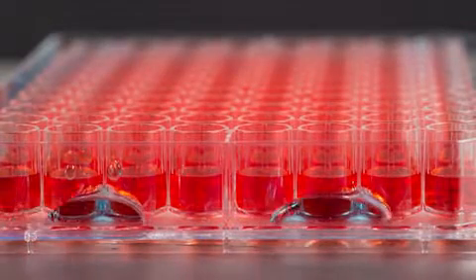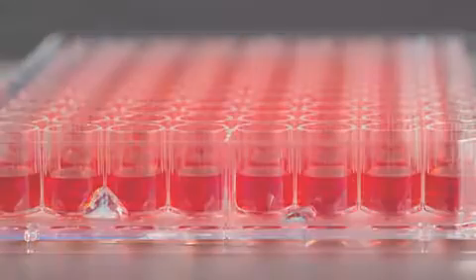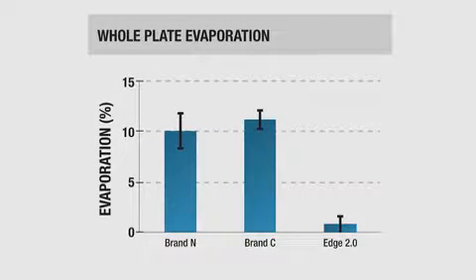Especially from the wells along the edge that are more susceptible to humidity change. The data shows that the Edge Plate significantly reduces evaporation, ensuring uniform performance across the entire plate. The Edge Plate significantly reduces edge effect. It's that simple and that superior.